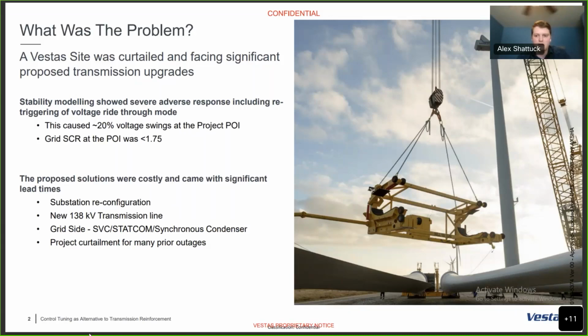But for this specific site, due to the low SCR, there are a couple of solutions. There's substation reconfiguration, moving breakers around, adjusting the planning contingencies so they weren't as severe, or so they would trip the plant offline during the fault instead of leaving it online and causing the stability issue. So the top solution was, let's change the contingency, let's change the grid so these problems aren't actually happening.